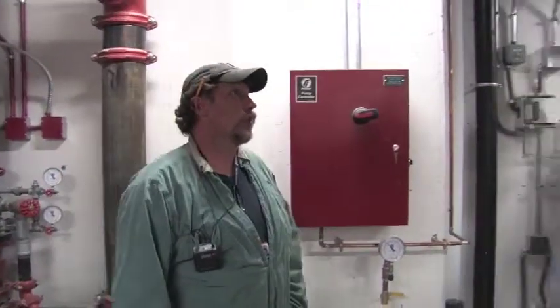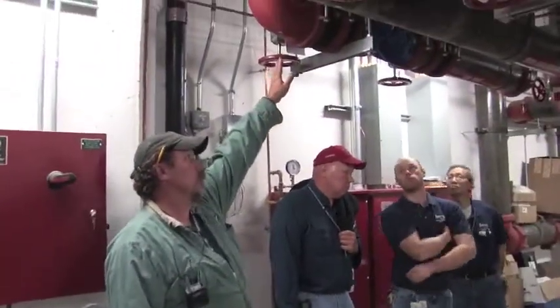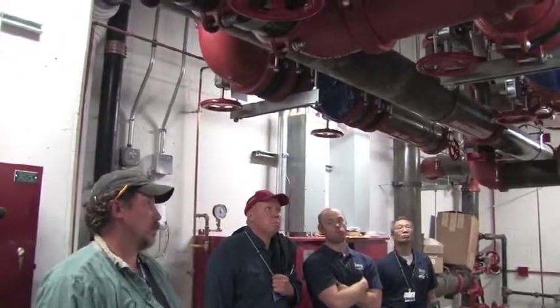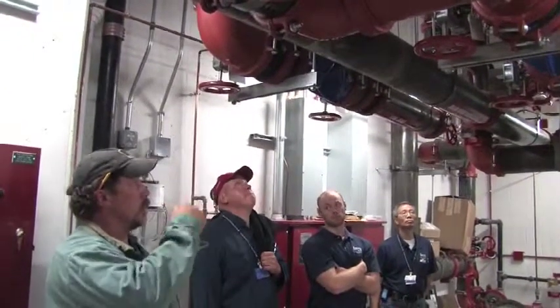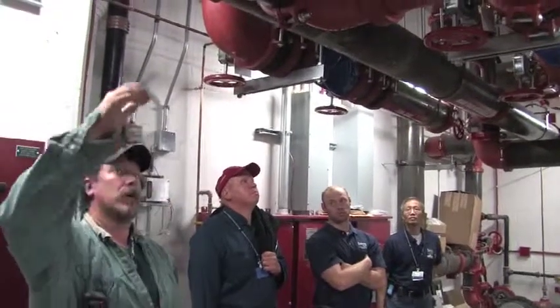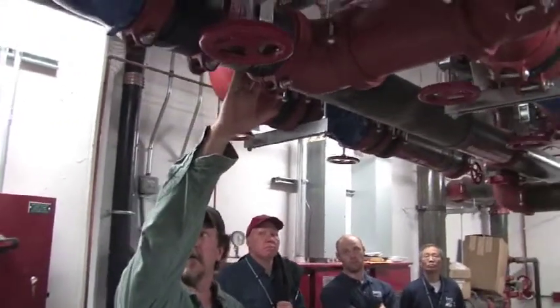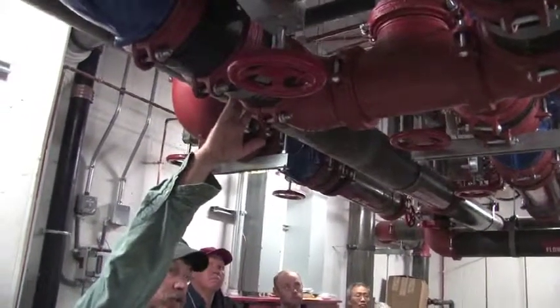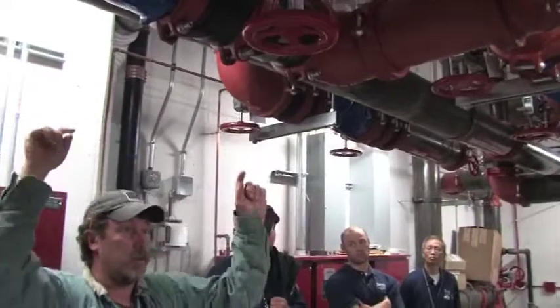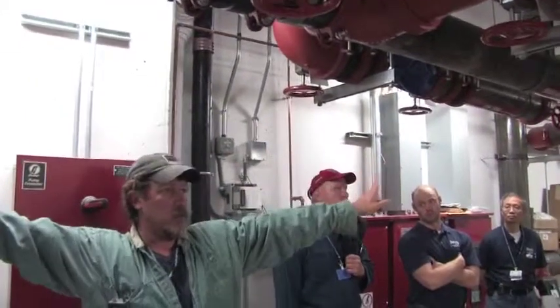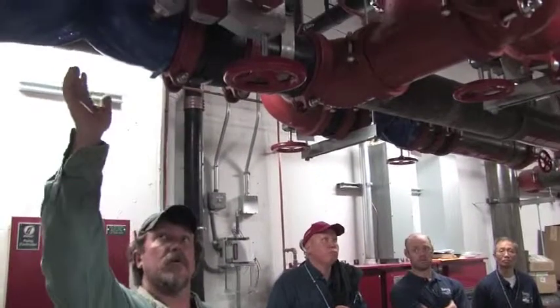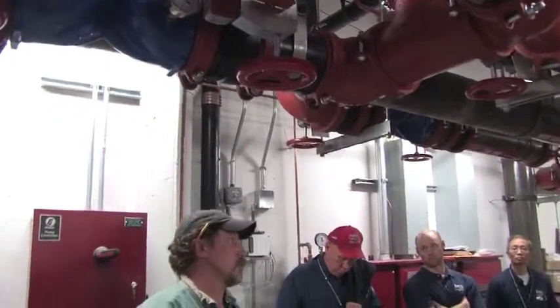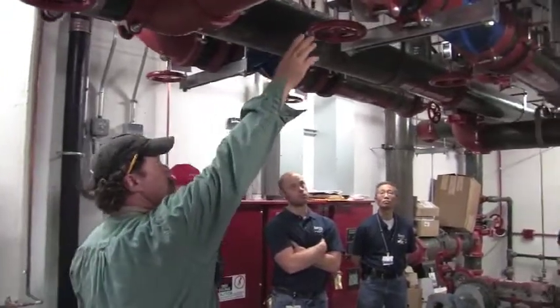We have two sets of pressure reducing valves. These bigger ones right here are for your low system. Going to come through and keep the pressure where it's supposed to be. And these smaller ones here are for the high system. All the pipe goes out into the main hallway, tees off, goes to both stairwells, runs up, and that's what it's doing there. But these are all just isolation valves for your pressure reducing valves. Same over here, just isolation valves.